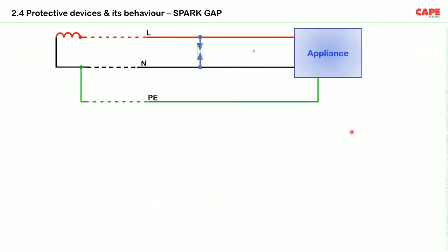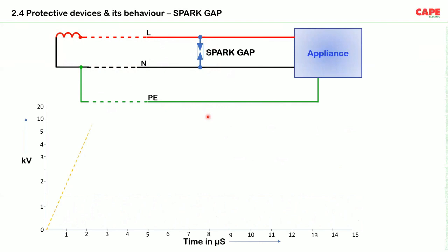Second is the spark gap. Imagine in the same place, we have a spark gap. Please understand that the power supply is coming from a transformer. Probably you have a long line, and the neutral also goes back. I have made a TN-S kind of system. You have a spark gap. The transient overvoltage is something like this on the dotted line.